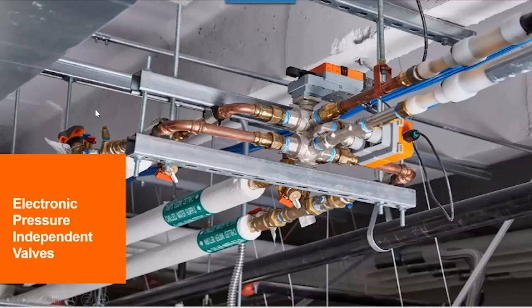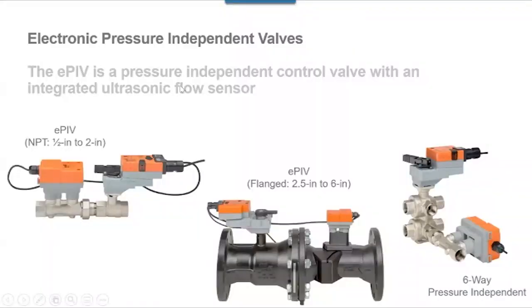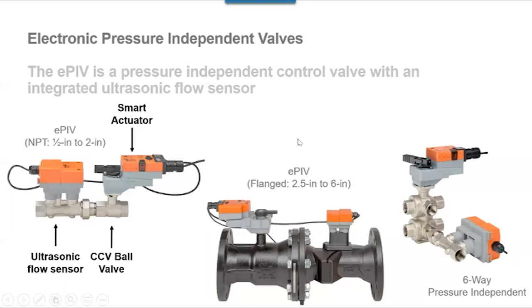So we addressed, back before 2010, we realized one of the challenges with pressure independent valves, especially on the larger sizes, was that they were relatively more expensive than a typical commercial HVAC project would see. So we looked at ways to address this, and what Belimo developed was what was called an electronic pressure independent valve. And again, as you see here on this drawing, it includes the control valve, in this case an ultrasonic flow sensor, and a smart actuator. There's software built into that actuator. So what is this doing?